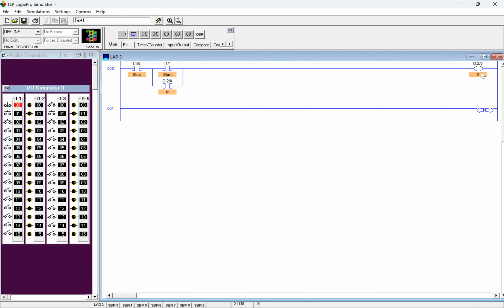And now when this closes. And so if I have this normally closed, which I want because stop, I need it to be closed. And I push on this, it closes that. When I release, this is now closed and my path is locked in. So it's a memory type circuit. It holds its value until I hit the stop. Okay.